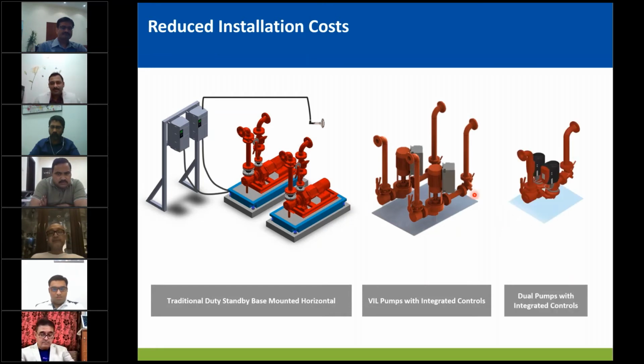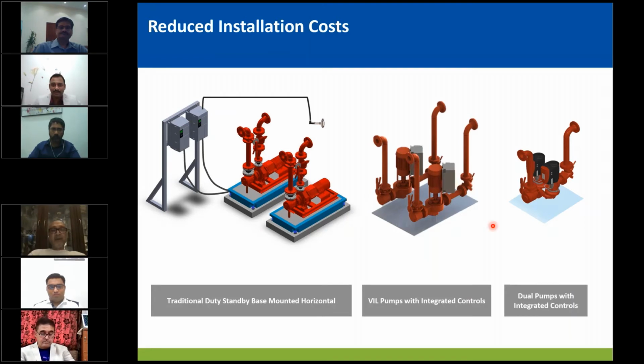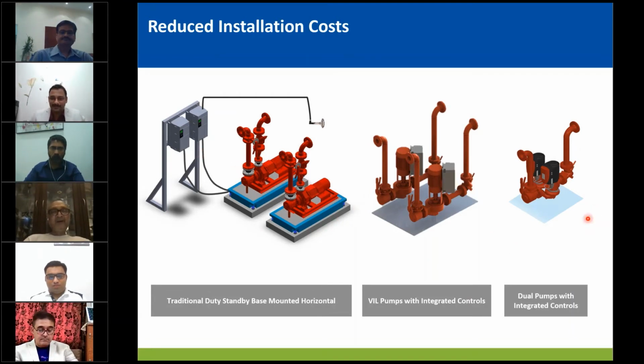Now, that doesn't stop there. You can still go for footprint optimization. There are twin or dual arm pumps available in the industry that have a casing with a single inlet and single outlet port and two rotating assemblies. That means two motors, two impellers, and two casing profiles here. So you only need one set of valves, and plus you get all the benefits of what we talked about in the previous optimization, like reducing all those accessories and space. Now integration doesn't stop here.